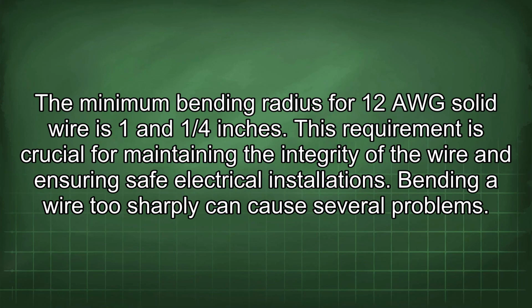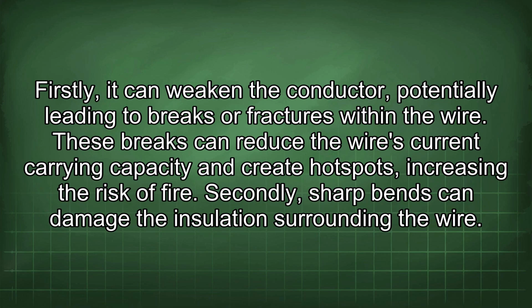The minimum bending radius for 12 AWG solid wire is 1 and 1/4 inches. This requirement is crucial for maintaining the integrity of the wire and ensuring safe electrical installation. Bending a wire too sharply can cause several problems. Firstly, it can weaken the conductor, potentially leading to breaks or fractures within the wire. These breaks can reduce the wire's current carrying capacity and create hot spots, increasing the risk of fire.